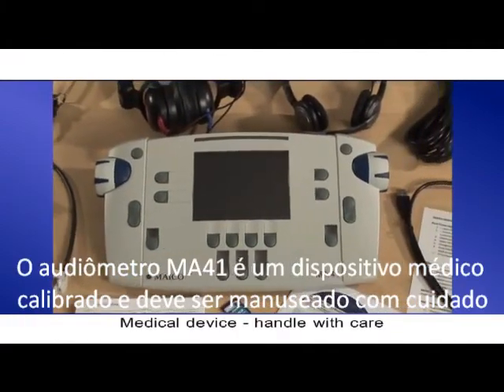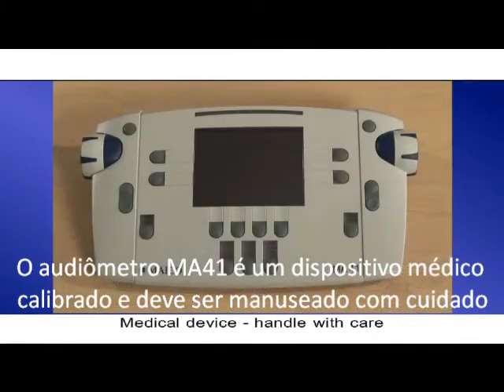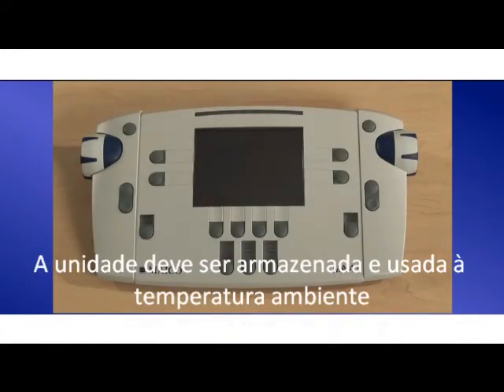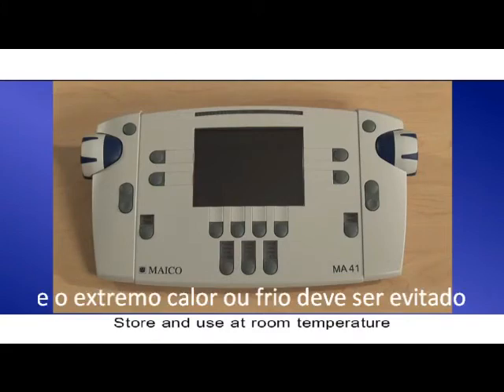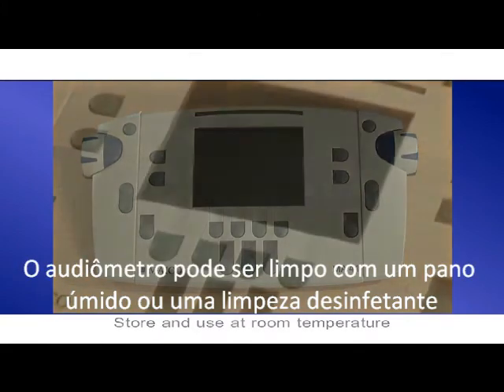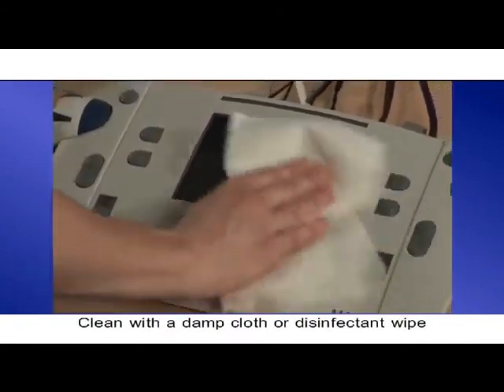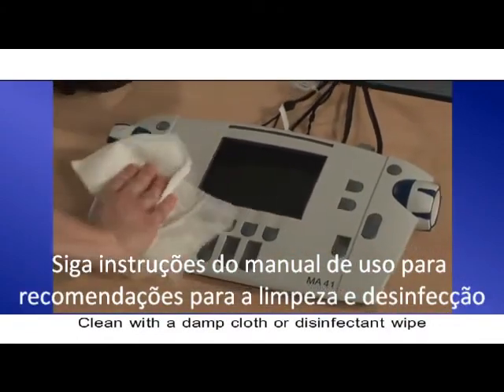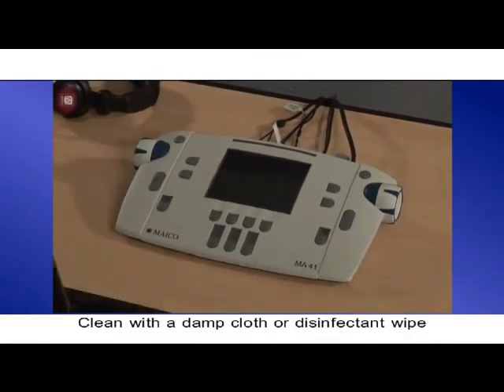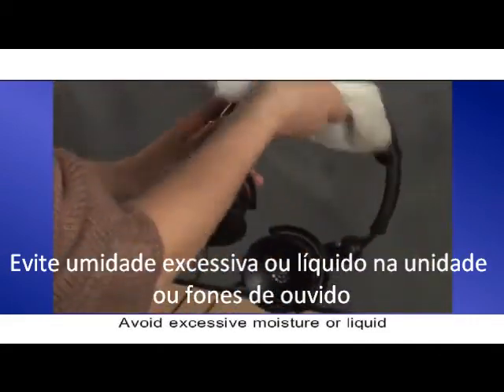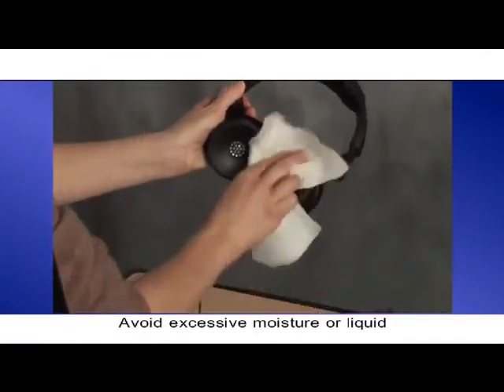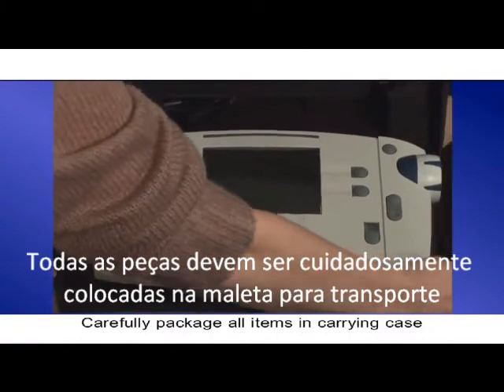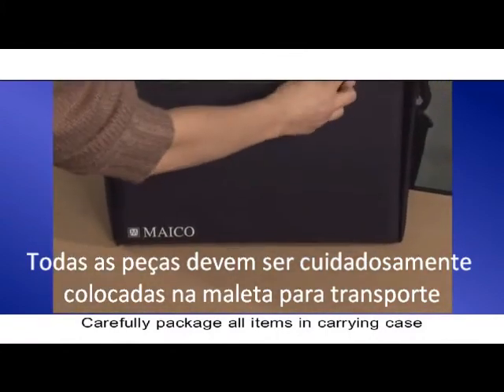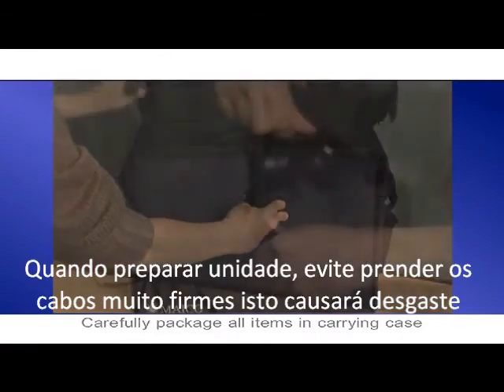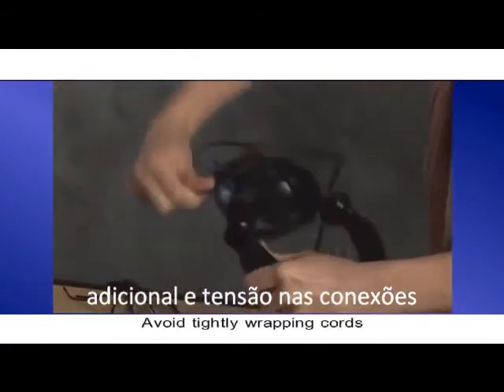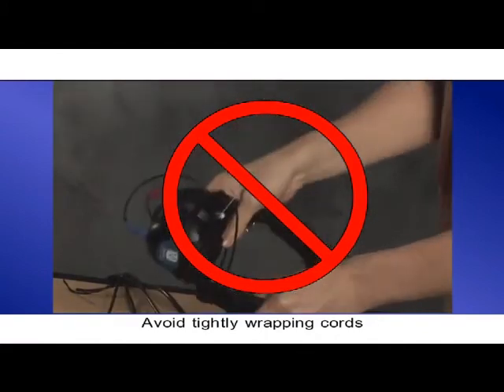The Ma-41 audiometer is a calibrated medical device and should be handled with care. The unit should be stored and used at room temperature, and extreme heat or cold should be avoided. The audiometer may be cleaned with a damp cloth or a disinfectant wipe. Please follow your facility's policy and recommendations for cleaning and disinfection. Avoid excessive moisture or liquid on the unit or headphones, as this may damage the internal components. All pieces should be carefully placed in the carrying case for transport. When packing the unit into the case, avoid tightly wrapping the cords, as this will cause additional wear and tear and strain on the cords and connections.